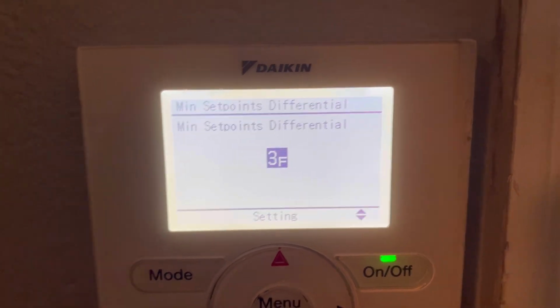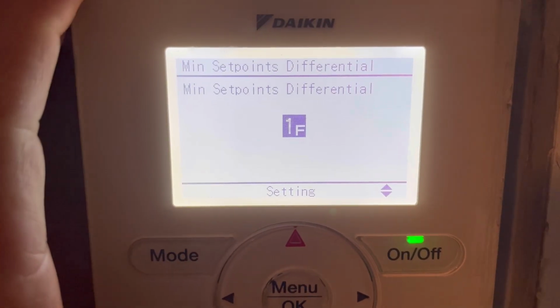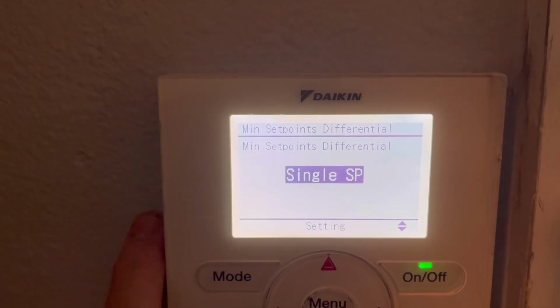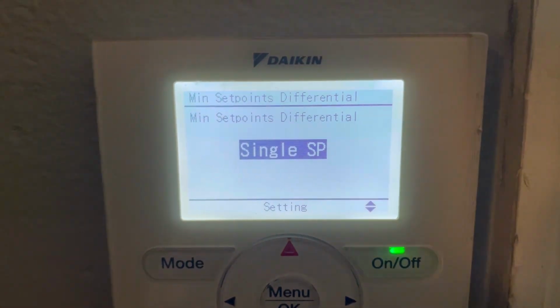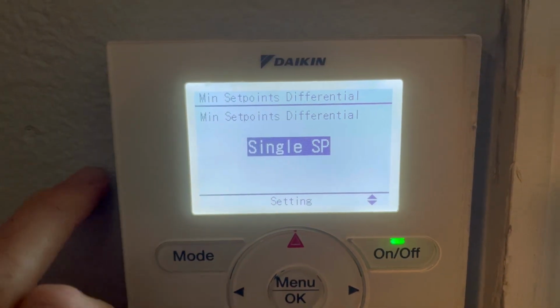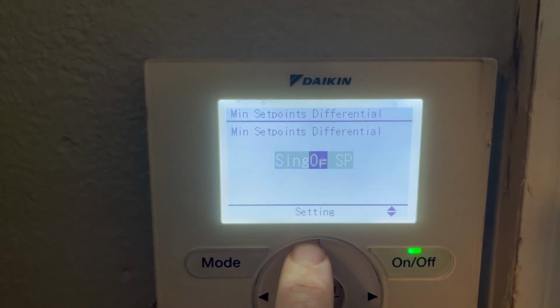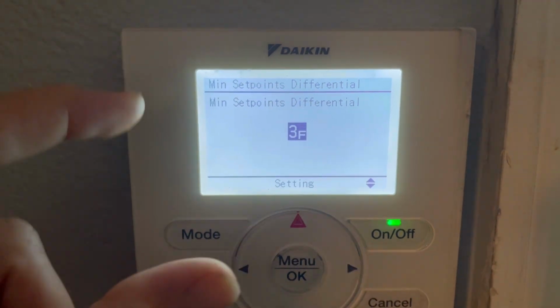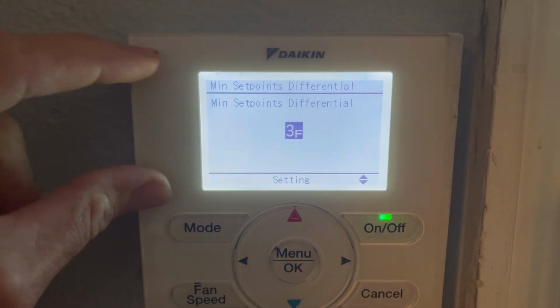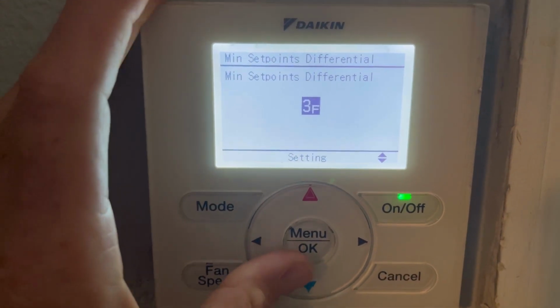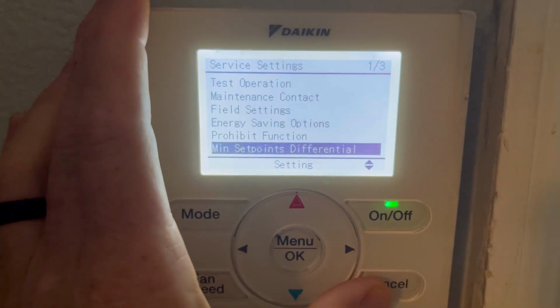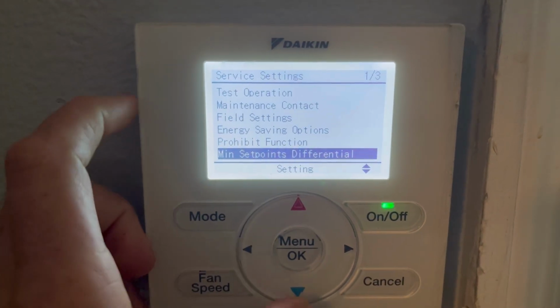Minimum set point differential. This gets a lot of people. From the factory, it comes set up as single set point. That means that in heating and cooling, it monitors the same set point. That means that if the system switches over, it's still going to try to maintain that same set point. I have it on a 3-degree deadband because I like there to be a difference between what my cooling set point's at and what my heating set point's at if I put it in auto. Okay, I'm going to hit cancel because I don't want to change that. When I do change that, it resets the thermostat.